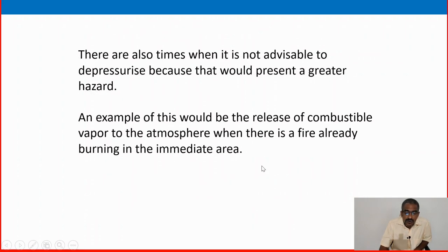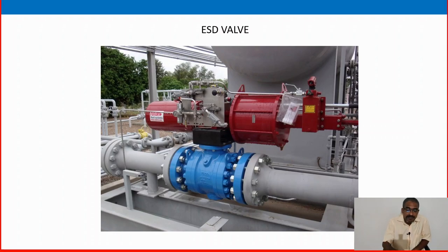There are also times when it is not advisable to depressurize, because that would present a greater hazard. An example would be the release of combustible vapor to the atmosphere when there is a fire already burning in the immediate area. And this figure shows an ESD valve.